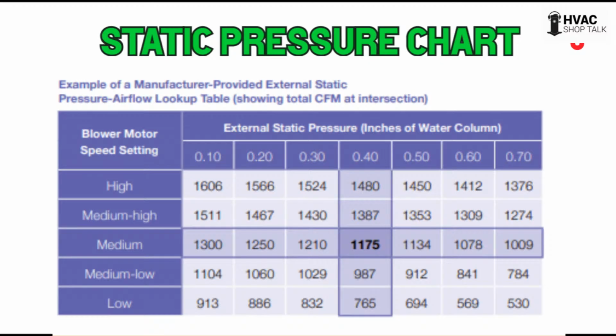When you change the blower tap, you have to measure again, because the static pressure won't be the same at a much lower blower speed. It will change and get reduced, so you have to look at the chart again. If low is too high for you, that's a problem you can solve certain ways, but we won't cover that here. Just know you have to keep measuring until your adjustments are done, and stick with the adjustment after that final look at the chart.